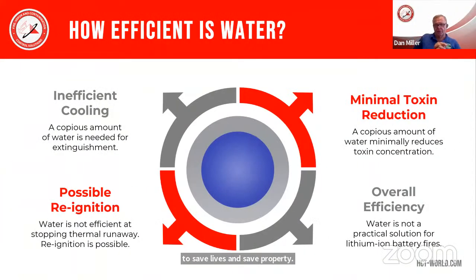Well, how efficient is water at cooling? It's pretty inefficient actually. Less than 10% of water typically provides cooling. The rest of it runs off without a temperature change. What does cool turns to steam, and steam is actually invisible and burns your skin, scalds your lungs clear down to the alveoli, which exchange the oxygen and carbon dioxide in your body—very, very harmful. With lithium-ion batteries, we often have reignition of the batteries after they've been cooled with plain water, because it has a high surface tension and doesn't get down into those base materials inside of that jelly roll or those layers inside of a flat aspect battery. And it doesn't neutralize the hydrocarbon electrolyte material.